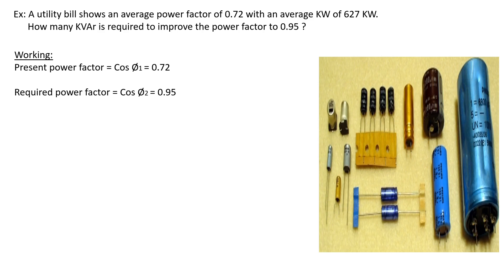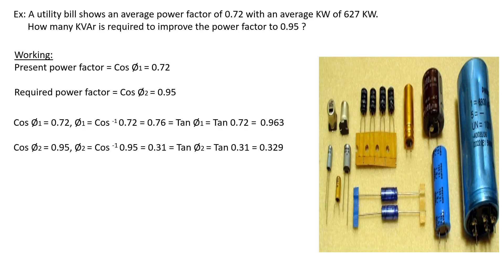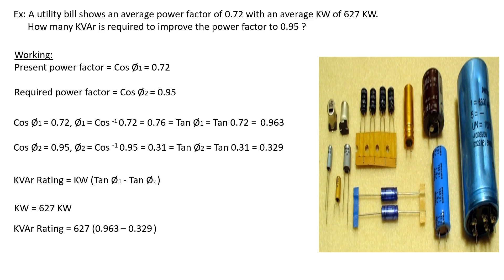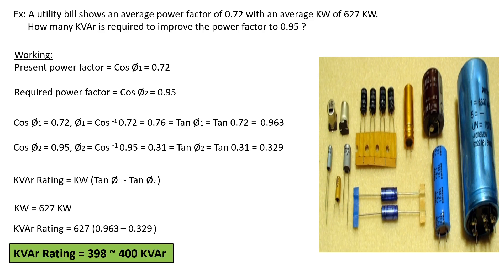The present cos phi is 0.72, so phi1 is the angle for 0.72. The desired cos phi is 0.95, so phi2 is the angle for 0.95. We calculate tan(phi1) and tan(phi2), then put all the values into the formula. Our answer is 398 kVAR, which can be rounded up to 400 kVAR — this is the rating for the capacitor bank.